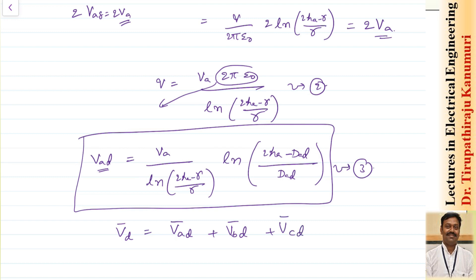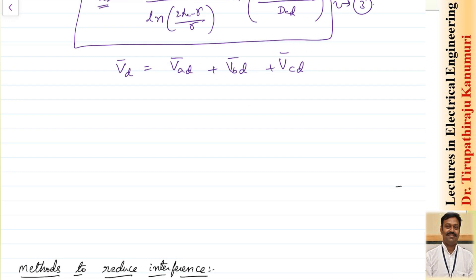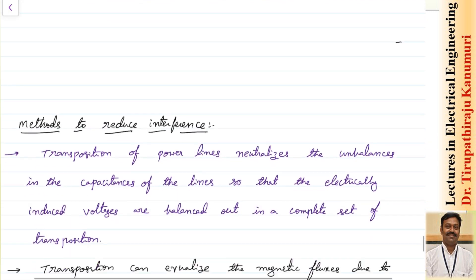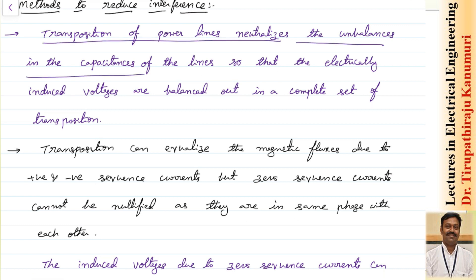Because of this, voltages are induced in the communication lines in each conductor. Similarly, I can calculate for conductor D using the same procedure. The question is how to decrease this value — how to make the electrostatic effect zero. This can be done by transposition of the power lines, which neutralizes the unbalance in capacitances, since all these effects come due to capacitance.